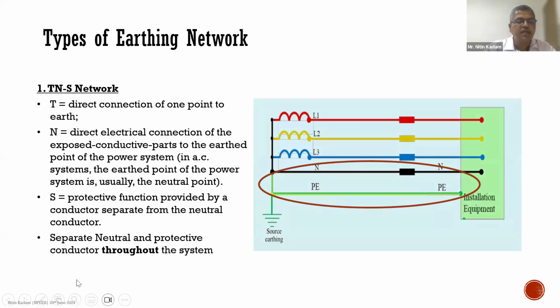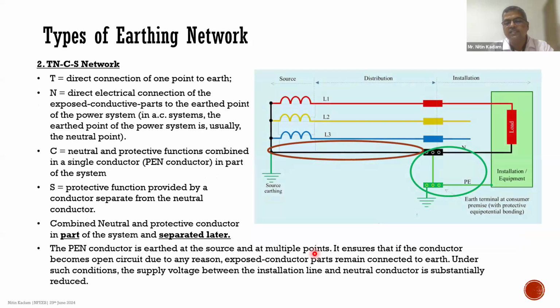Now, if you see here, in this network, you have the three phases coming to the building installation, followed by a neutral and an earth. So basically, this is a 5-wire system where you have a neutral and a protective earth conductor coming right from the secondary of the supply transformer to the building installation. These are dedicated neutral and dedicated earth wires coming from the star point of the secondary of the transformer, which is supplying the building installation. When we talk about the TNCS network, again for the installation, you have a 5-wire. But there is a difference here where you have the PEN conductor, a common earth and neutral conductor, which is coming from the secondary of the transformer up to the main earthing terminal. And here it gets separated into a separate neutral and separate earth.